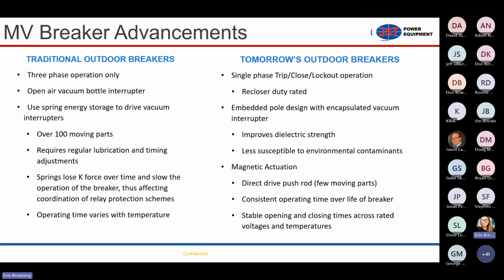Embedded vacuum interrupters have proven to have a lot of benefits from a dielectric standpoint, especially in really high contaminant environments. Think a lot of dust, for example. You don't end up with dust and particulates all over exposed components of the vacuum interrupter endpoints. So an embedded pole combined with a magnetic actuator that has very few moving parts requires virtually no maintenance throughout the course of its life because it is fully self-contained, and independent of environmental factors. So it has consistent operating speed over the life of the breaker and across all temperature ratings of the breaker. There's no springs that slow down over time.